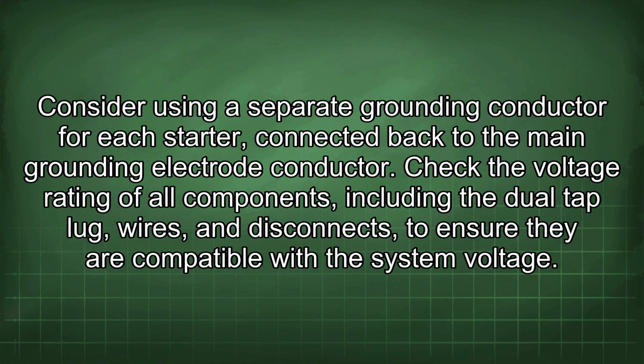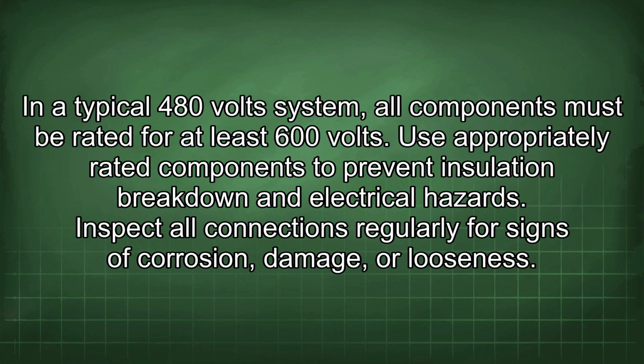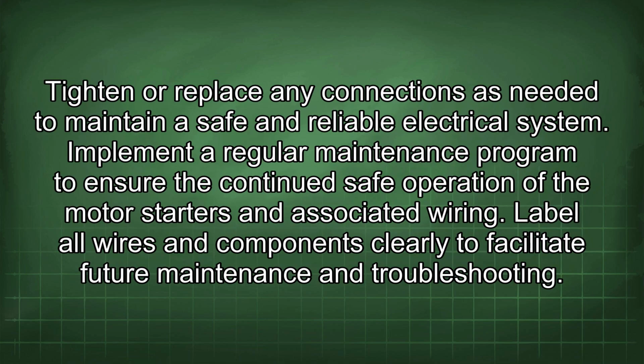Check the voltage rating of all components, including the dual tap lug, wires, and disconnects to ensure they are compatible with the system voltage. In a typical 480 volts system, all components must be rated for at least 600 volts. Use appropriately rated components to prevent insulation breakdown and electrical hazards. Inspect all connections regularly for signs of corrosion, damage, or looseness. Tighten or replace any connections as needed to maintain a safe and reliable electrical system.